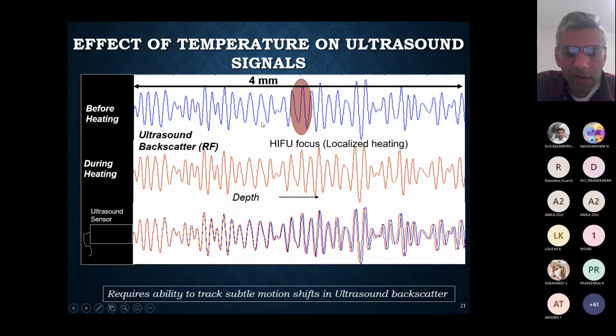I'm showing that schematically here using actual ultrasound echoes. This blue is the ultrasound trace before heating. There's a spot here where the heating takes place. The red is where you have heated the tissue and then done a measurement. If you visually look at these, you don't see any change. The echoes look exactly identical, but it helps to overlay them one over the other, and you can start to see that the echo is shifted, right? The blue is shifted with respect to the red.